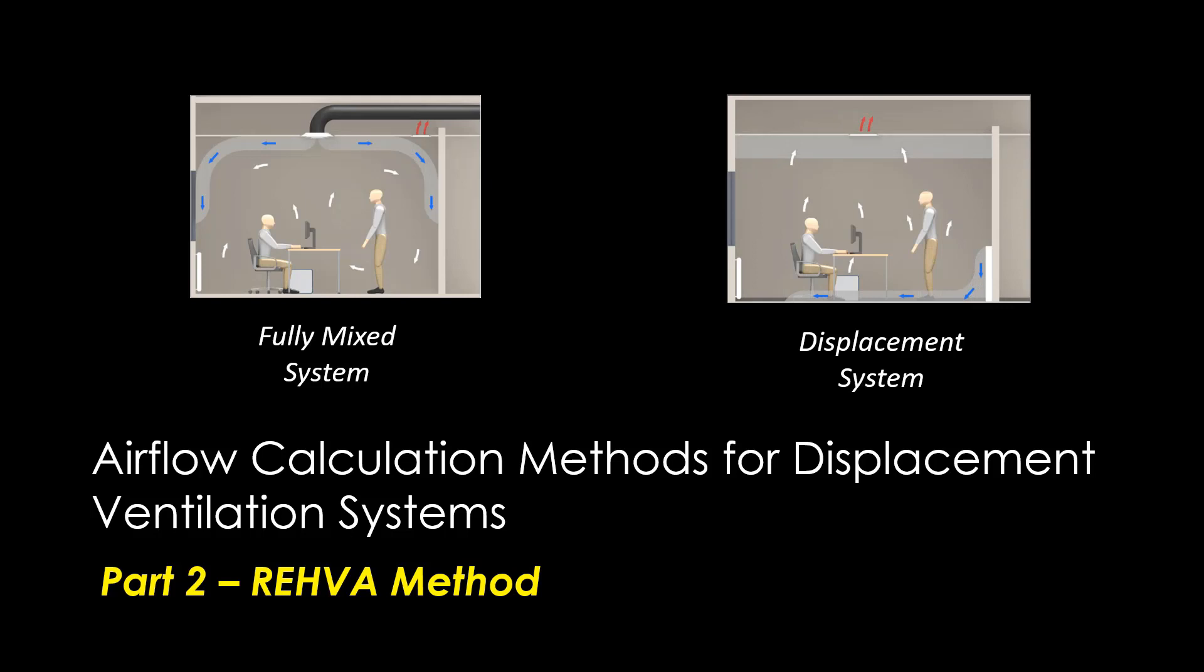In part one I covered the ASHRAE calculation method which I would recommend watching before jumping into this part two where I will be describing the European REHVA method. The two methods differ slightly in that the REHVA process does not involve applying correction factors to individual heat gains but is based on applying typical space temperature gradients to calculate acceptable supply and return temperatures. The difference between the supply and return temperatures is then used to calculate the required airflow to accomplish the space sensible cooling.